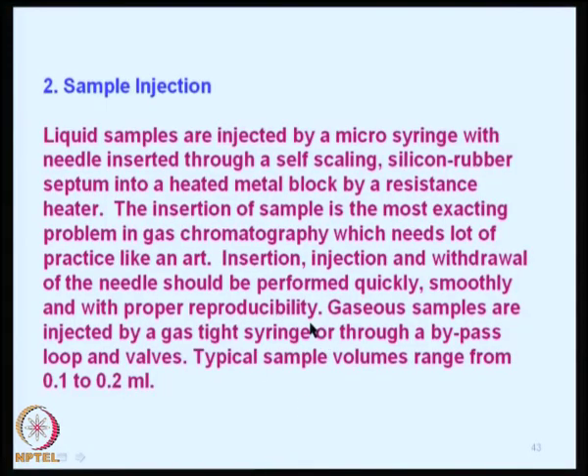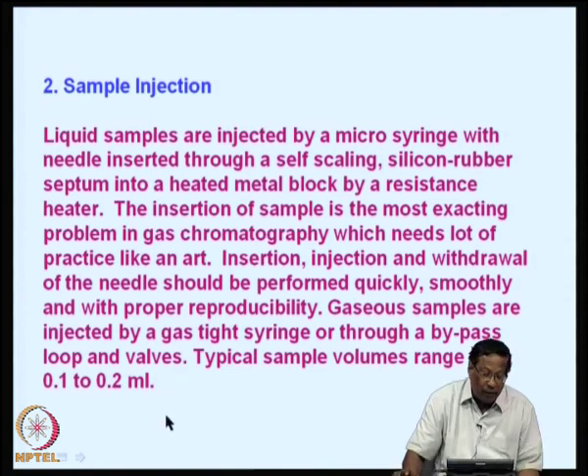For a gaseous sample, you have to take a gas-tight micro syringe, suck the gas into it, and then insert it as usual. It is also possible to introduce the gas through an arrangement of loops and valves. Typical sample volumes range from 0.1 to 0.2 milliliters, that is up to 200 microliters.